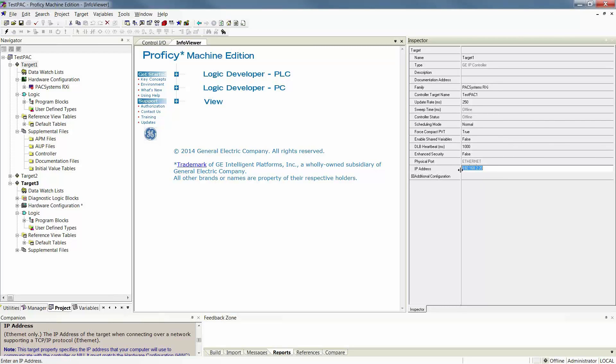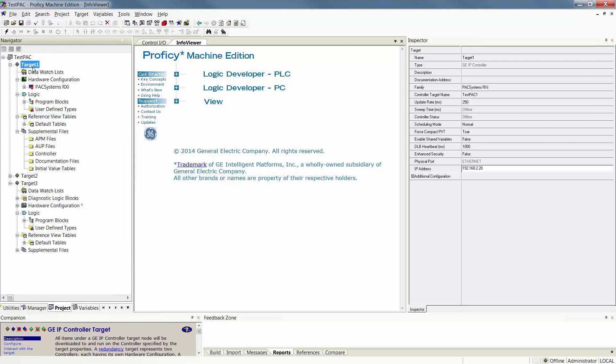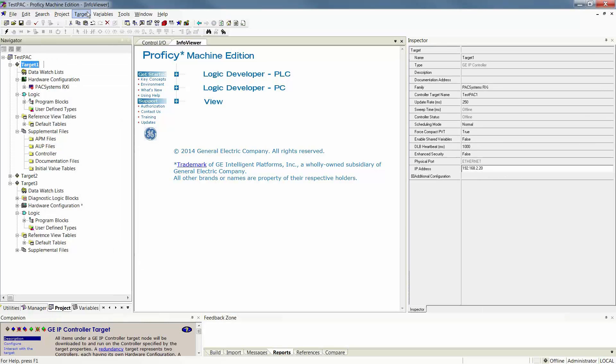The next step to connecting, aside from plugging in the right physical port selection and IP address in this case because I have selected Ethernet, is to ensure that my target is the active target within the project. This is extremely important if you have multiple targets like I do in my project. If you simply have one target, it will always be the active target. You will notice that target 3 is currently the bolded or highlighted target. That is because it is now the active target. If I'm unsure of this, there are many ways to check. You can either right-click on the target you would like to make the active target and ensure that the set active target is grayed out. In my case, it is not, and therefore I need to select it to make this the active target.